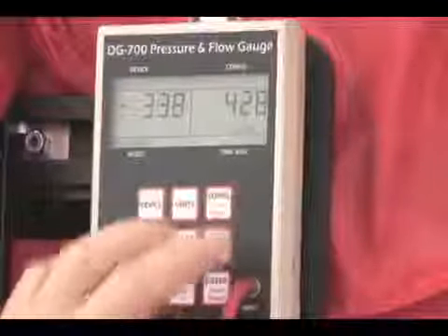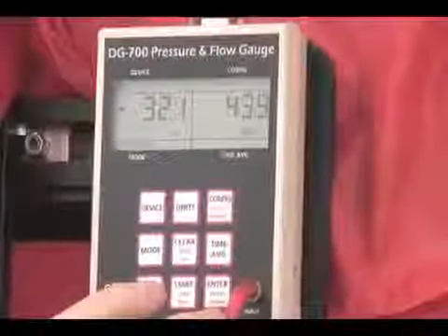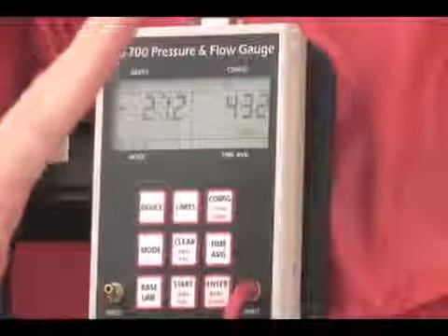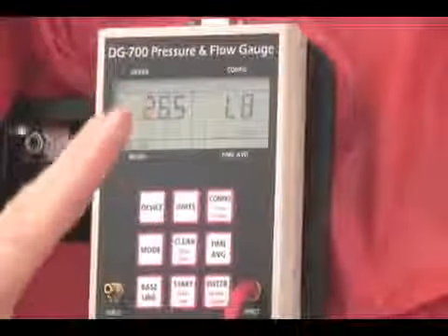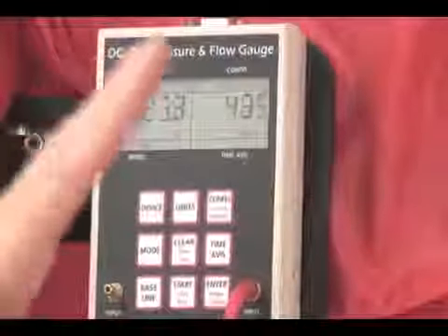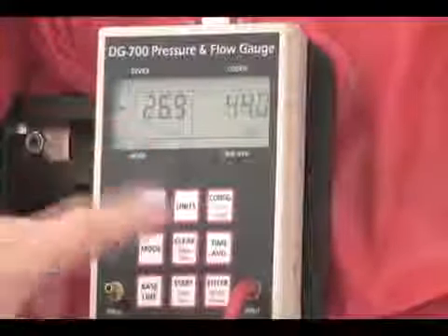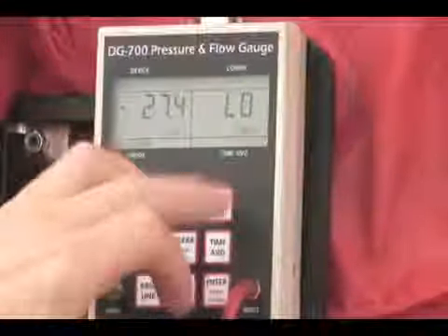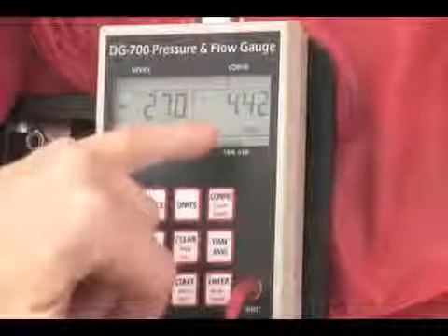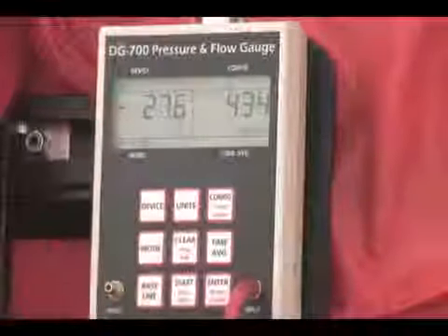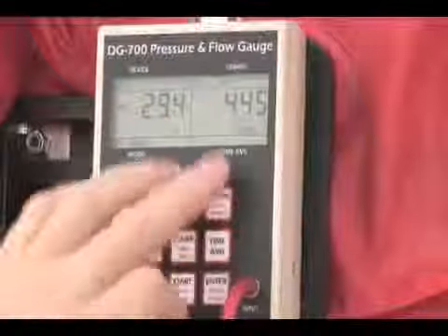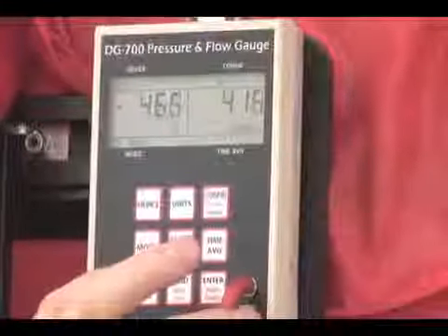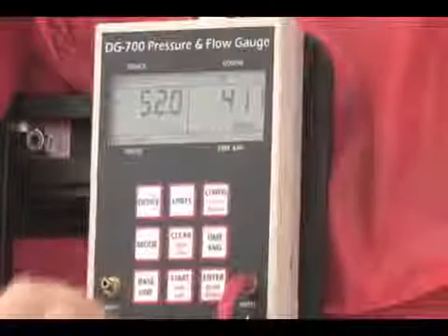So even if the pressure drops, as we're showing here, you'll notice that the CFM is not dropping very much, because it keeps extrapolating back up to 50 and answering the question mathematically: what would the flow be if I was at 50? So even though we're only at 27, we're still extrapolating back up to 50. The fan is running so slow now that our flow pressure is a little bit low, so let's speed it back up again. Notice again, the flow is not changing very much, because again, it's extrapolating to 50 pascals.